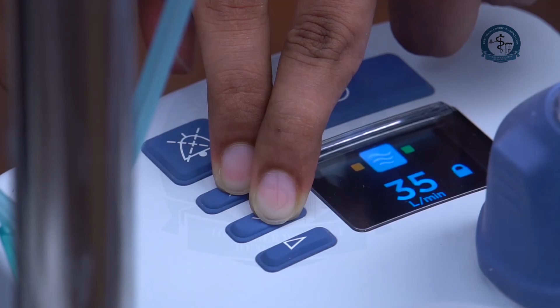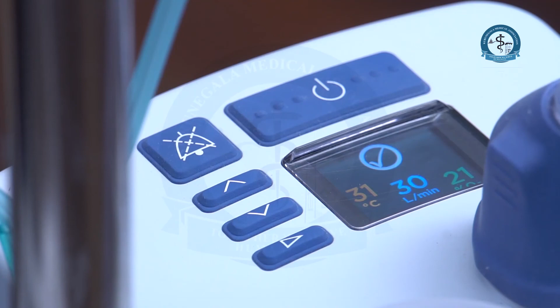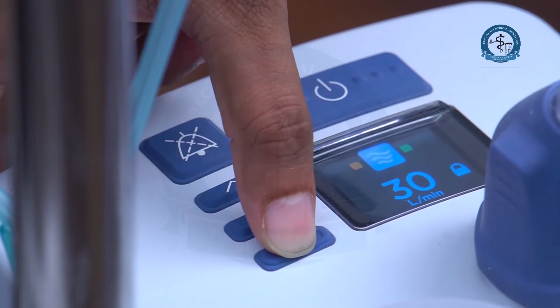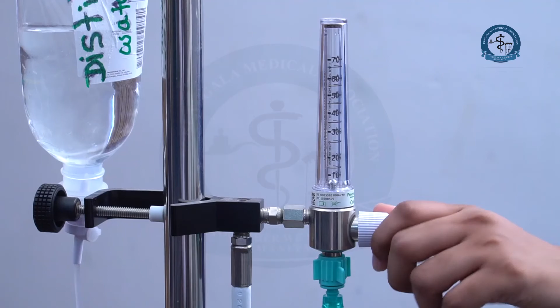The third parameter we are going to control is the fraction of inspired oxygen, FiO2. This parameter is controlled by adjusting the oxygen supply to the machine. This is done by adjusting the oxygen flow regulator as shown here. Normal air contains 21% of oxygen. By adjusting the oxygen flow, we can supply up to 100% oxygen to the patient.